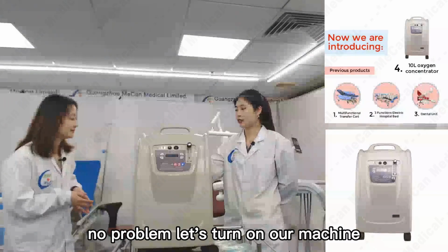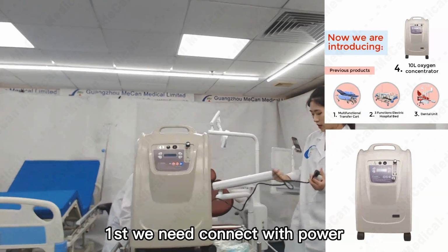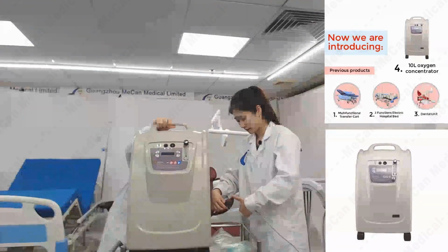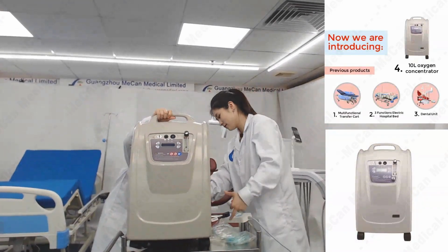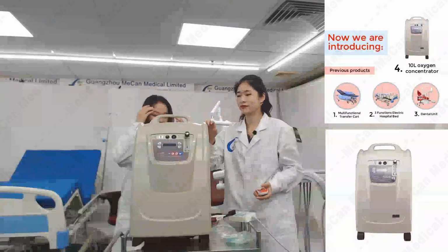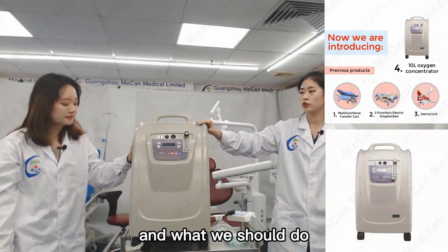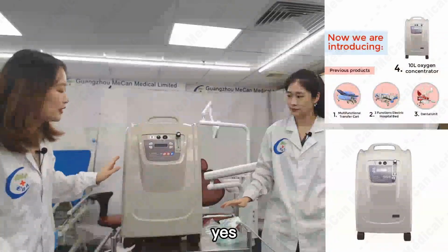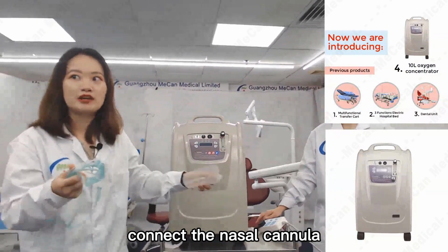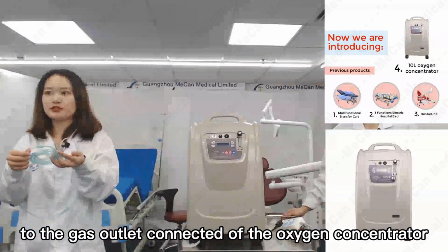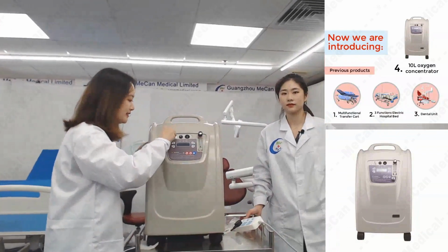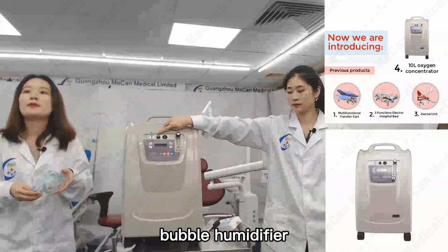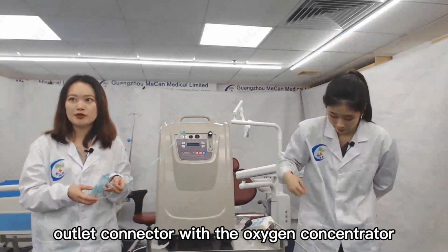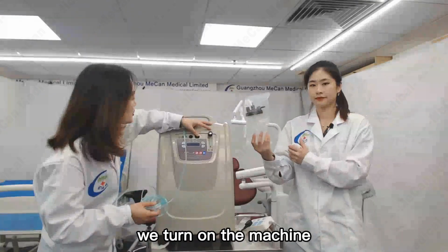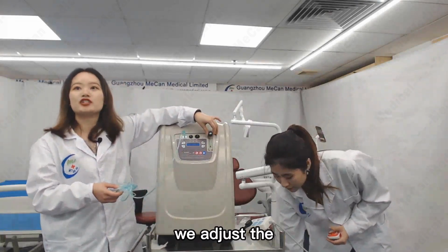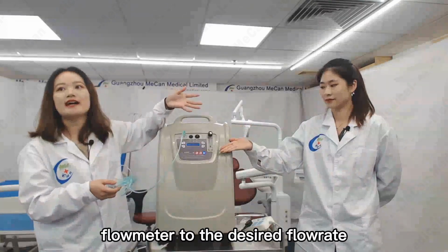Yes, no problem, let's turn on our machine. First, we need to connect the power. And what should we do after we connect the power? Yes, we connect the nasal catheter to the gas outlet connector of the oxygen concentrator. Let me show you. Or, if using the bubble humidifier, connect it to the outlet connector of the oxygen concentrator. With the oxygen concentrator turned on, we turn on the machine and adjust the flow meter to the desired flow rate.